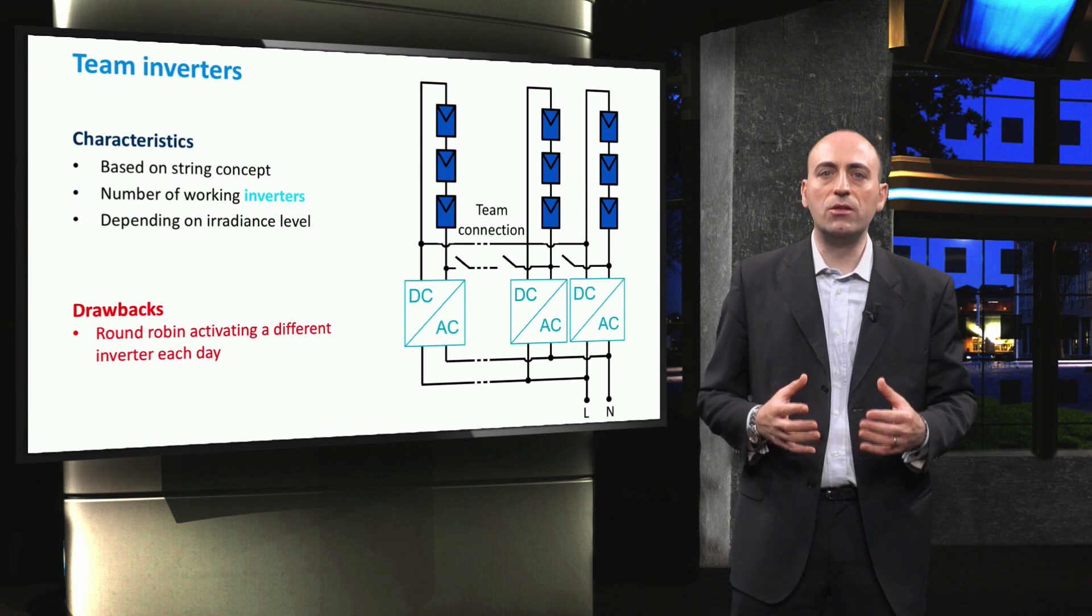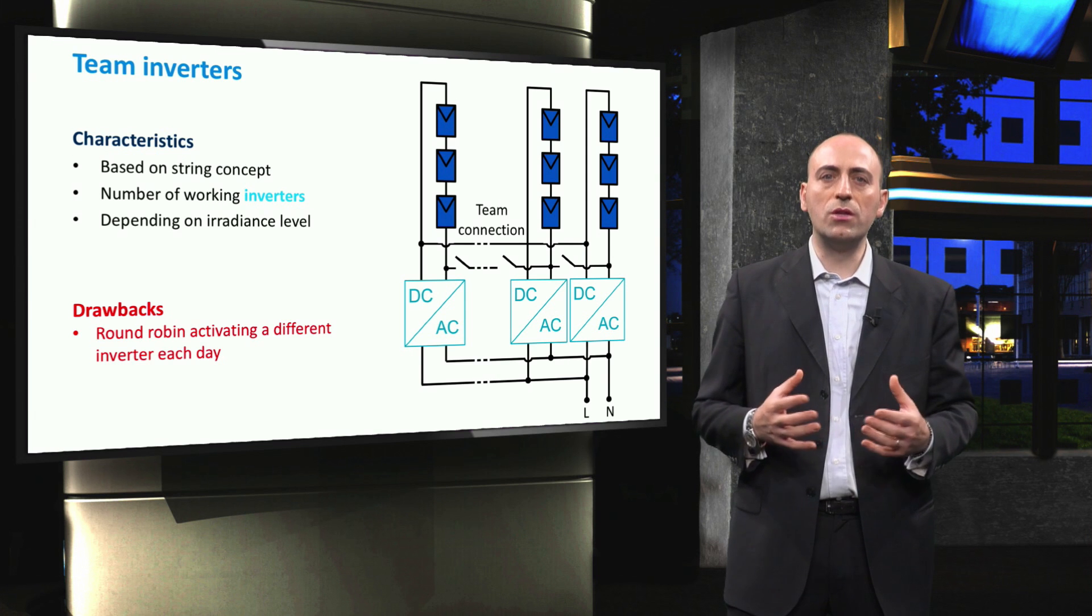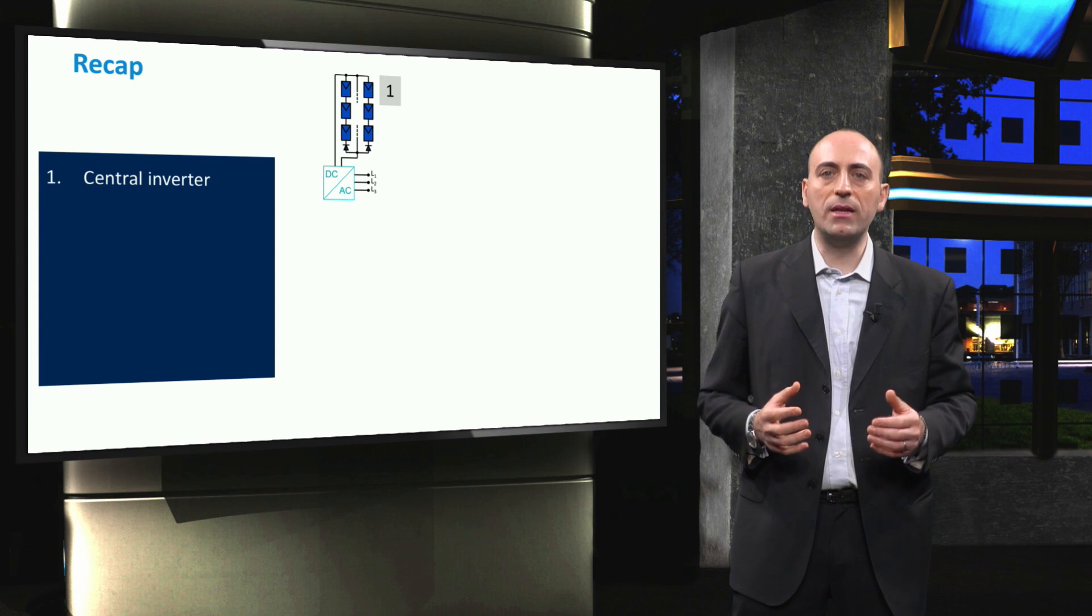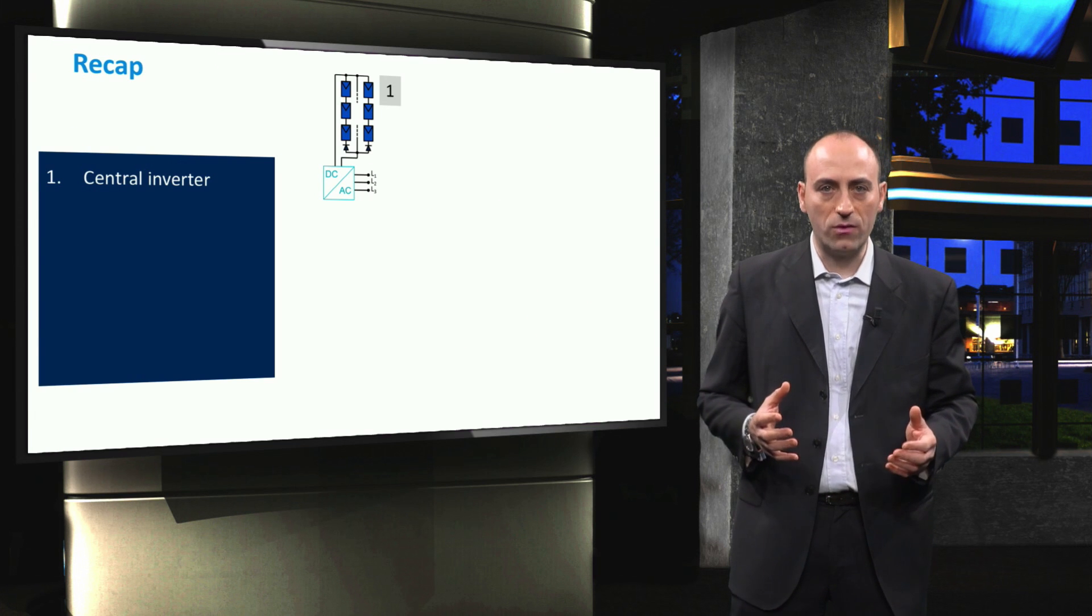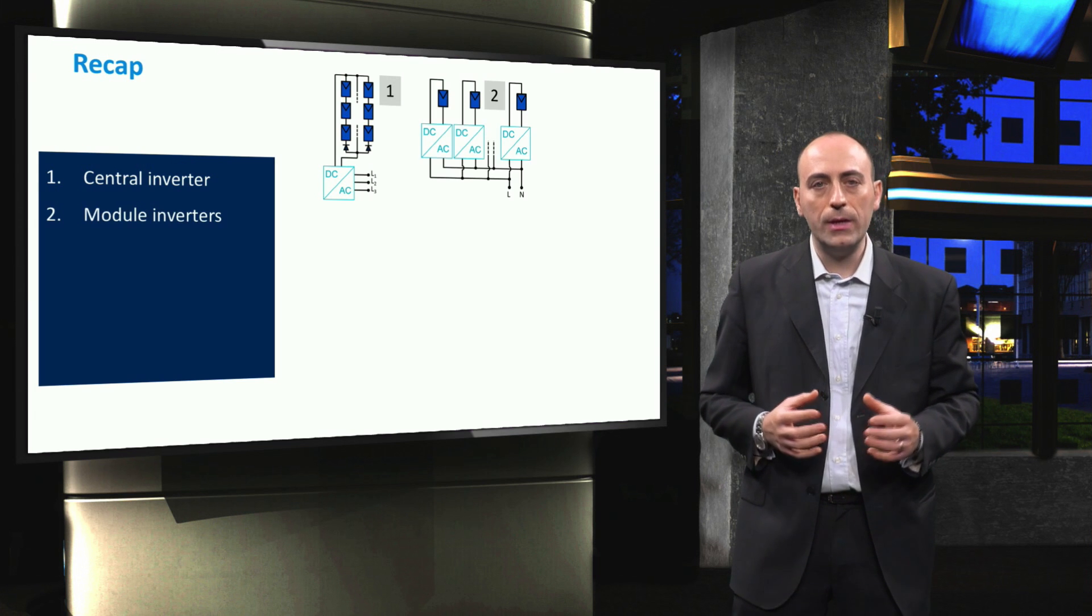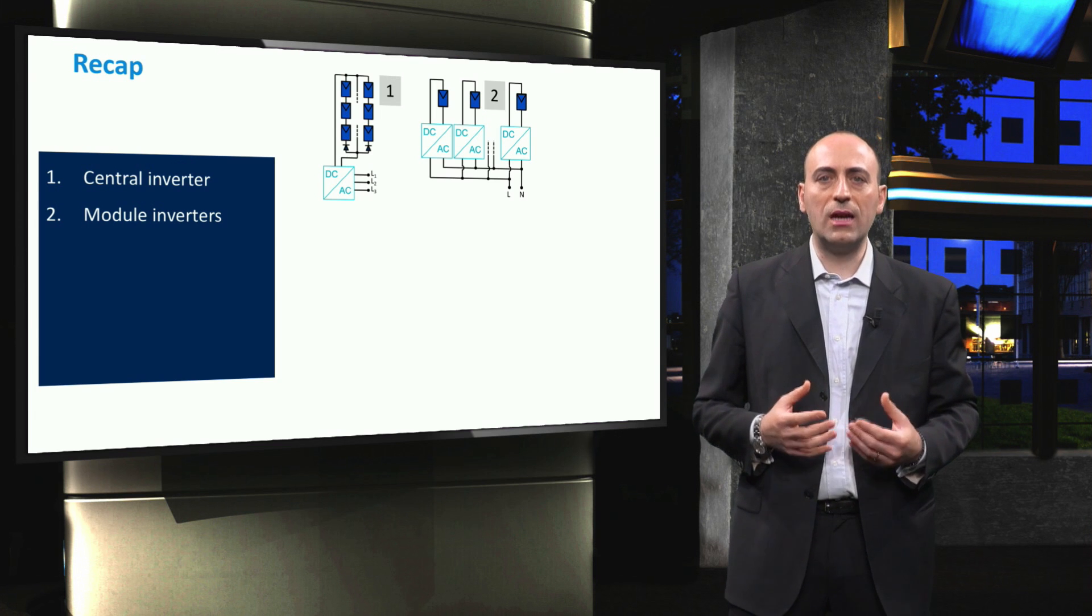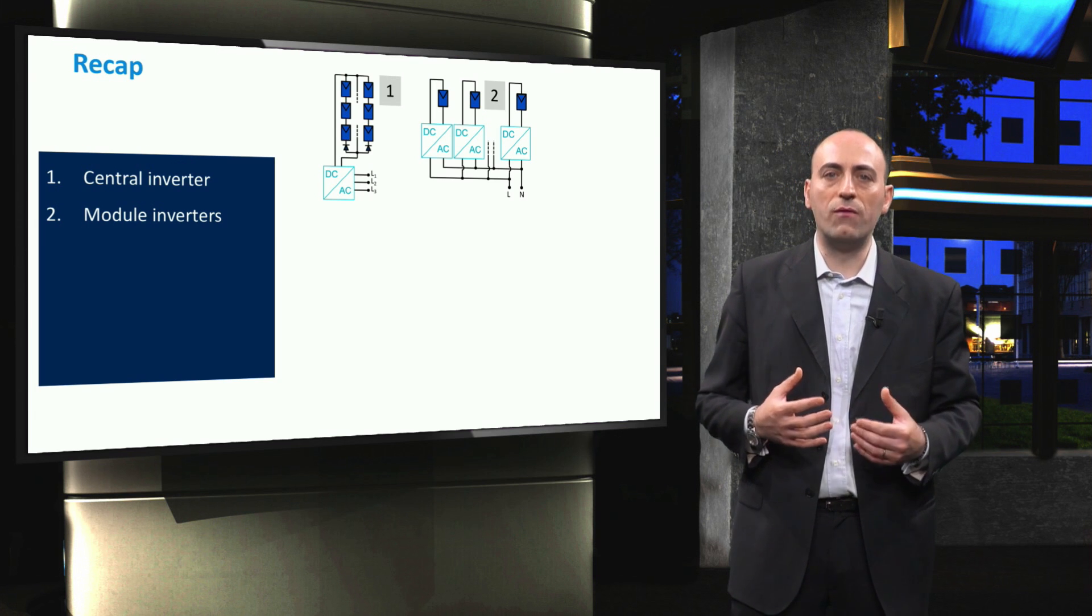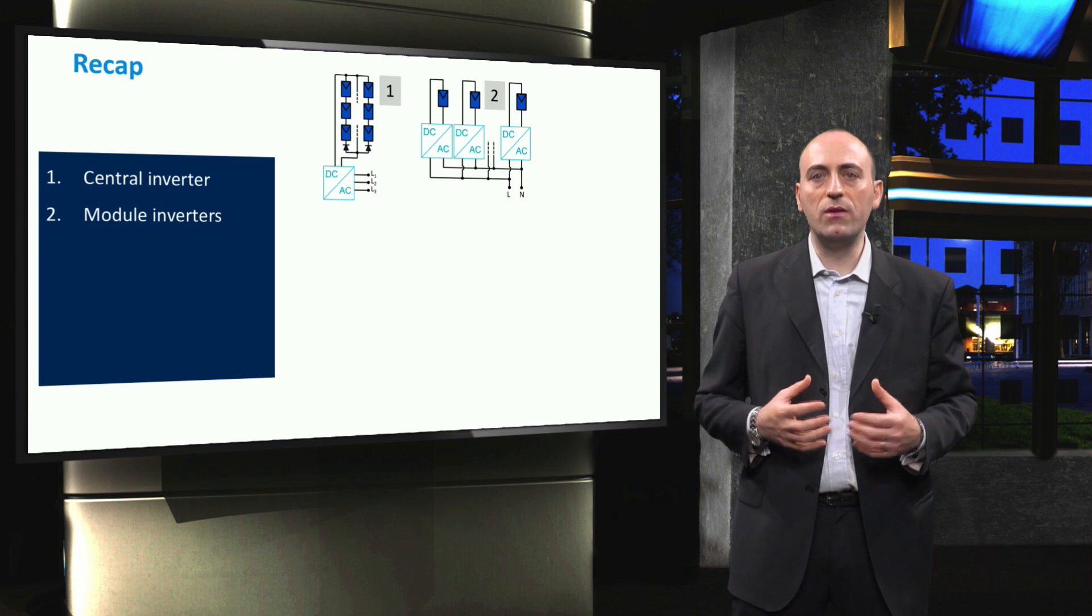Of course, with this master-slave fashion, we need to have an additional intelligent circuit that basically makes a round robin in the usage of all these inverters, in order to not always use the same one. To sum up, in this video we have seen six main installation concepts for solar inverters. The first and easiest architecture is the central inverter, which connects in parallel different strings directly to one single tri-phase inverter. The second type features module inverters. Here, some micro inverters are directly connected to one or a few PV panels. As we have seen, this design makes the system more flexible and easier to expand. On the other hand, the cost can become prohibitive if there is a high number of modules.